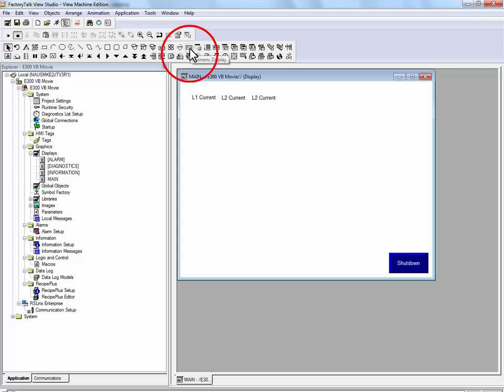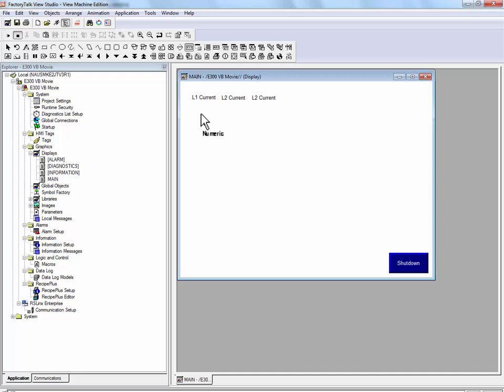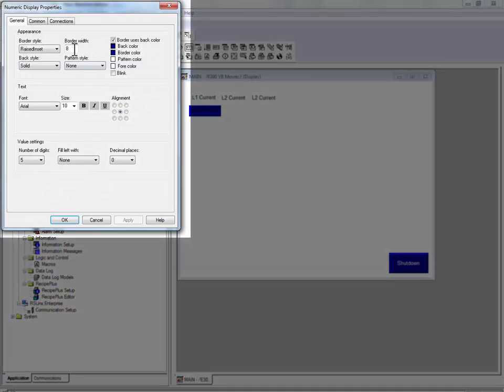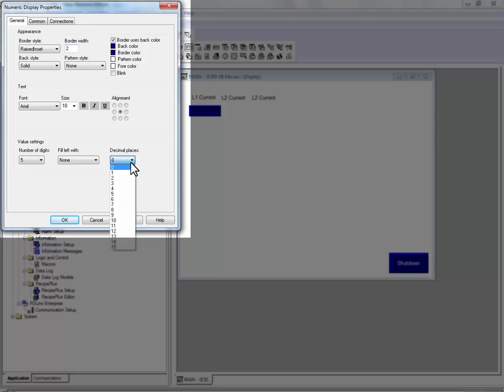We'll use the numeric display to display the actual current draw of the electric motor. Because the current value from the E300 is scaled by a factor of 100, we will display two decimal places of precision.